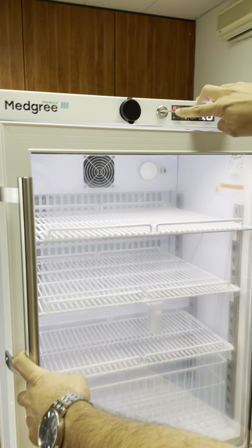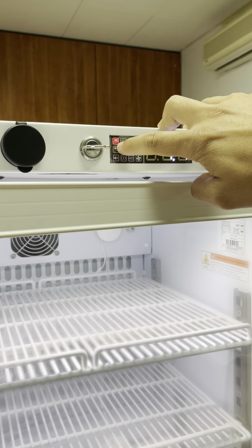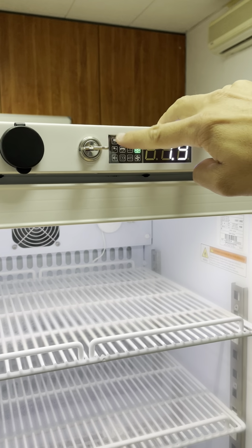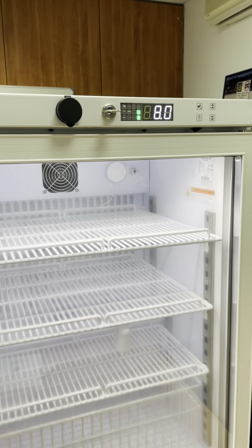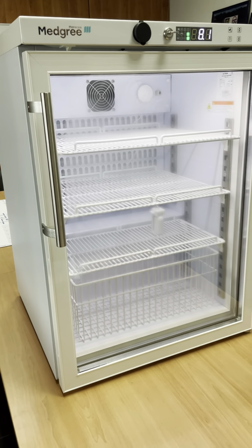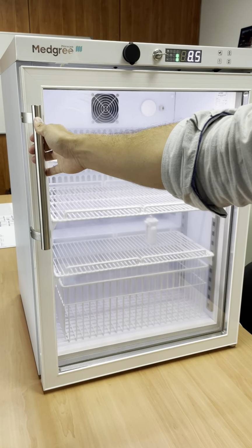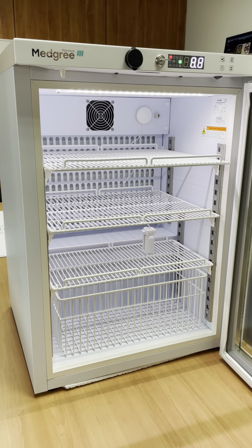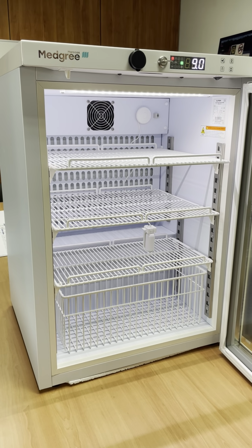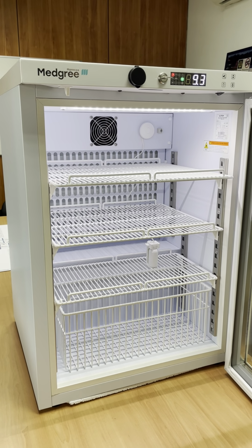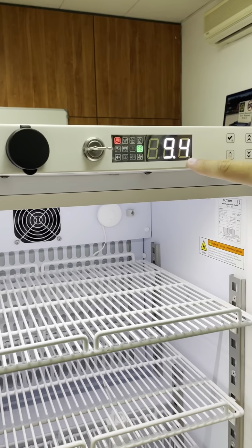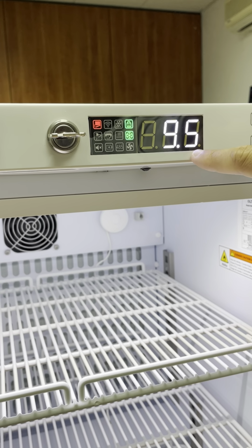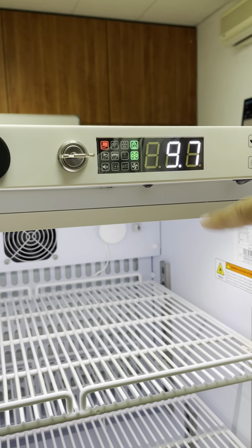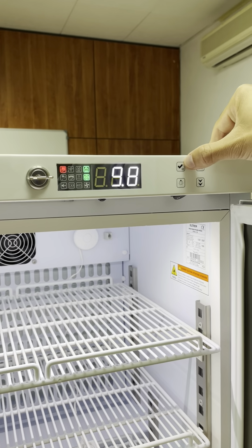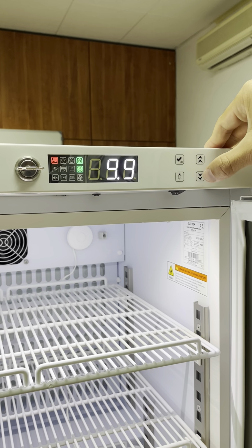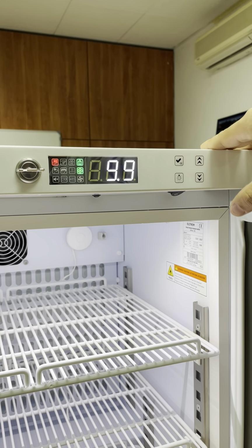When you open the door, you have the open door alarm showing here. When you close it, it will clear again. So, important things here. Now the temperature is going up. I will force a high temperature alarm and an open door alarm, so I'll keep the door open for some time to force this. You can see the temperature of the air going up automatically. So you are all the time reading the temperature of the air, probe 1. And then if you touch this button, you can see the temperature of the product probe.